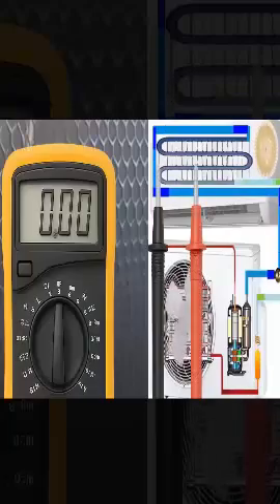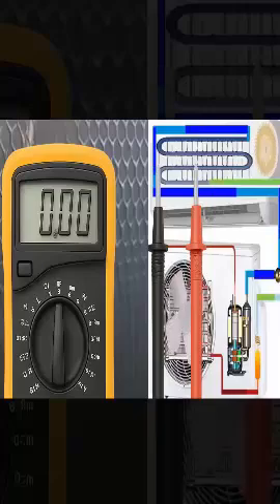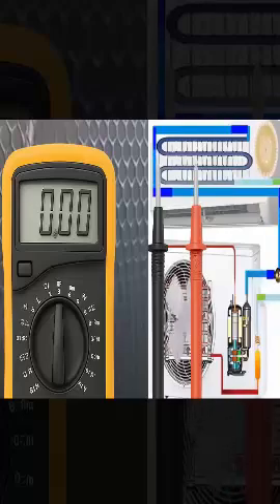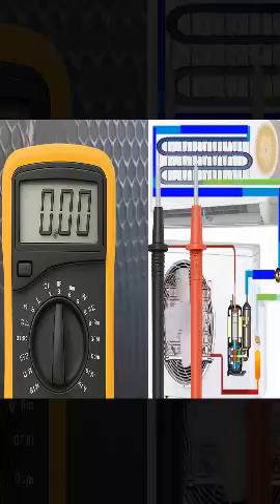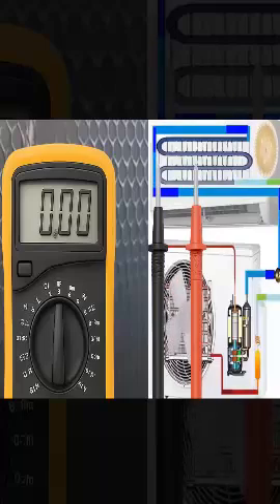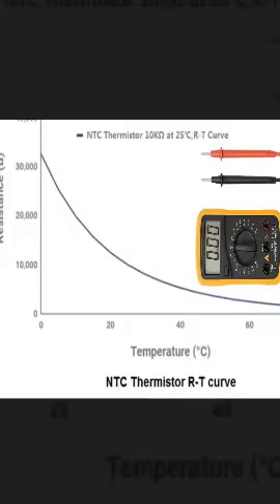To diagnose a sensor fault, technicians use a multimeter to measure its electrical resistance and compare it with a reference chart according to the temperature. They also check the physical condition of the wiring and connectors to rule out mechanical damage or corrosion. If the fault is confirmed, the sensor must be replaced with an original or compatible one, always matching the resistance curve. Steps to test the outdoor temperature sensor of the outdoor unit.